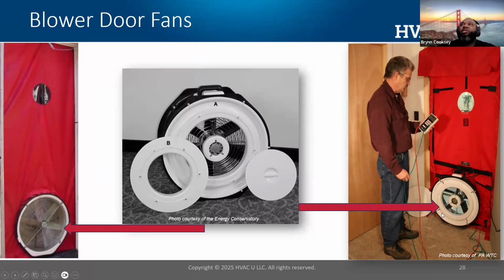Blower doors are essential for evaluating if a home is going to be suitable for a heat pump install. If I have an excessively leaky house and I have to air seal, remember I don't have the backup of the muscle of the gas furnace. That gas furnace can put out really, really warm temperatures and it can hide building issues. That heat pump, even though it's physically capable to do the work, I don't have that muscle, I don't have that high temperature to support me. So if you put in a heat pump, part of your load calculation should include a blower door.